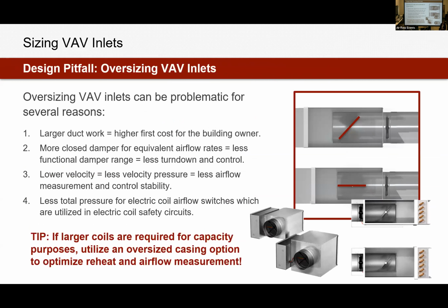A different solution to upsizing the inlet valve is maybe just upsizing the casing. A lot of people like to increase their box size for acoustics and capacity instead of just airflow measurement. So there is the option to keep your inlet valve size the same. Maybe we stick with that 8-inch inlet, but we increase our casing size to a size 10. That allows a bigger casing, which is less sound generation, and a bigger casing for a larger coil. So we can get higher capacity out of the coil if we're running the same airflows.